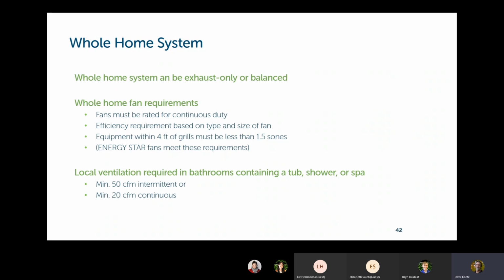Local ventilation is required in bathrooms that contain either a tub, a shower, or a spa. They have to be a minimum 50 CFM intermittent or 20 CFM if they run continuously. And those local ventilation fans do not have to meet the sound requirements or the efficiency requirements above. They can basically be anything if they're not part of the whole house system.